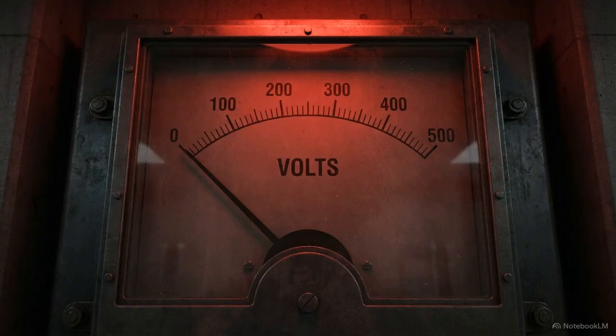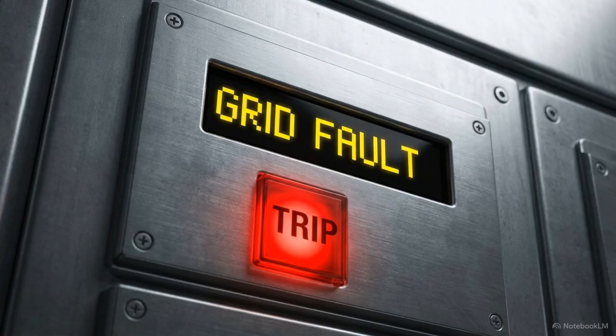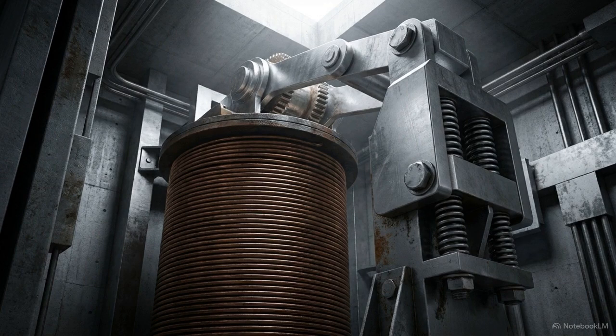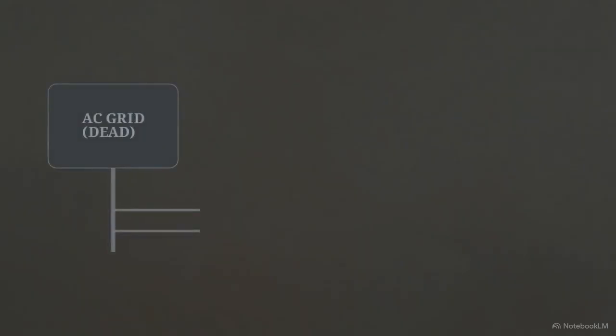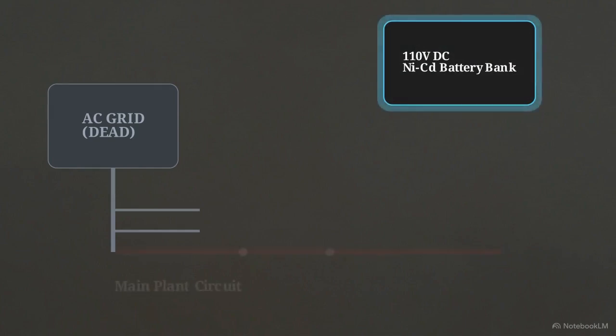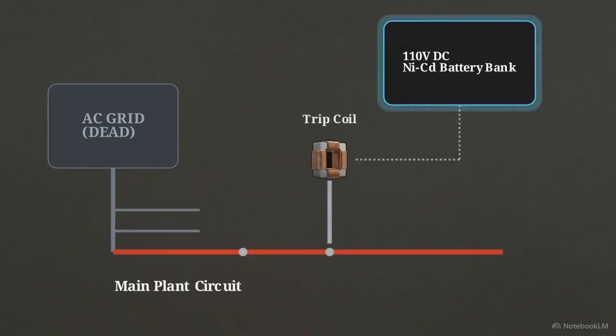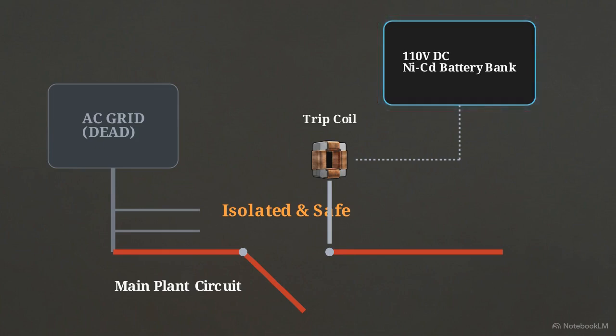The moment the voltage drops to zero, an engineering paradox emerges. The protective relays detect the blackout and issue a trip command to open the vacuum circuit breakers. But the mechanical coils inside those heavy breakers require electrical power to actuate. This is where an independent 110-volt DC nickel-cadmium battery bank takes over. Completely isolated from the AC grid, the DC batteries hold enough stored potential to forcefully punch the breaker trip coils, physically isolating the massive plant circuitry from the dead grid.